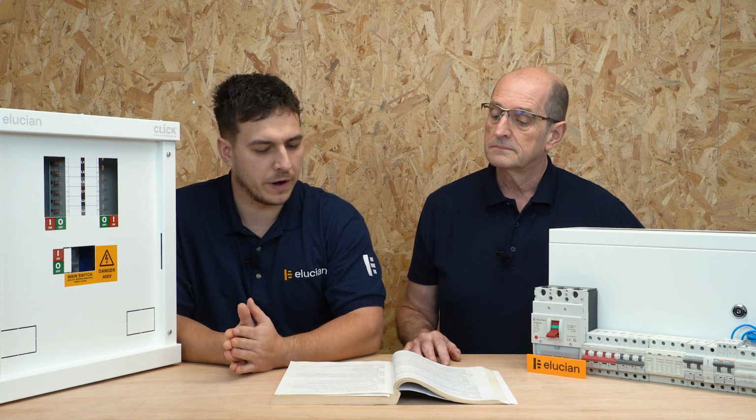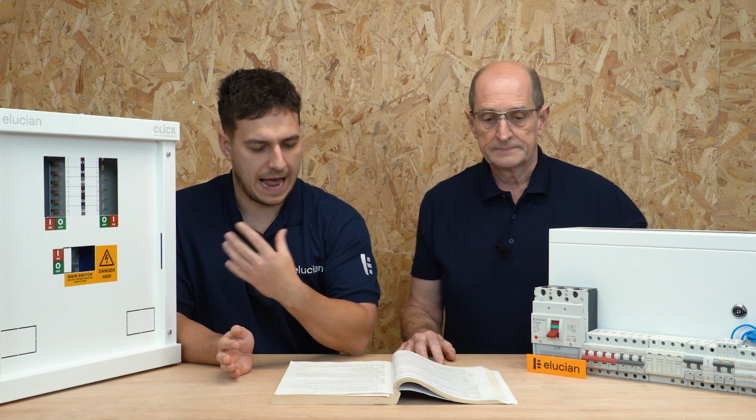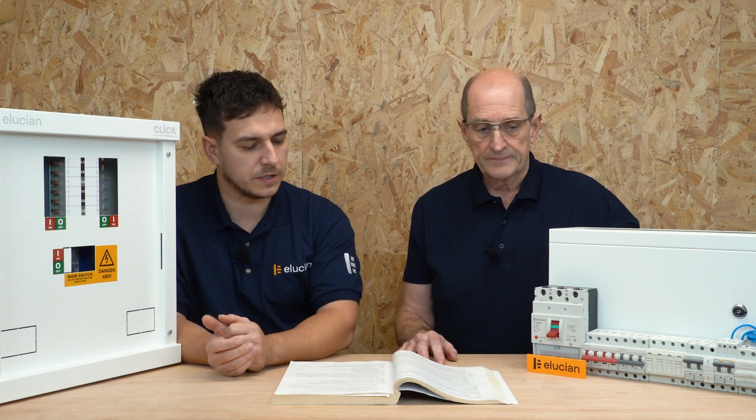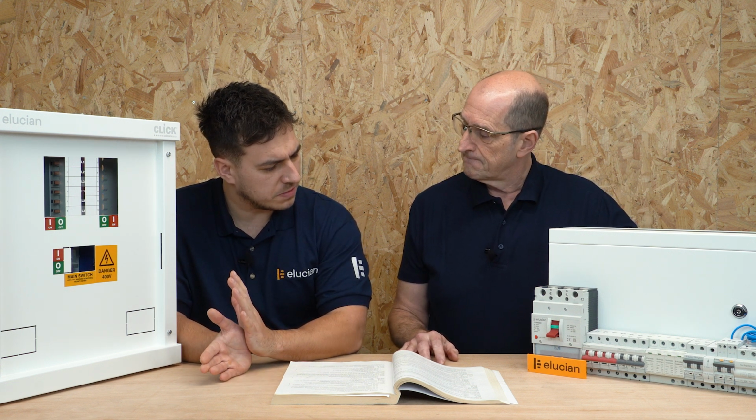Now, that's very important when it comes to the type of installations you're going to be doing when it comes to three-phase and some of the emerging technologies that we've already spoken about. So, subtle differences between the 4 different types, isn't there? Yeah, I mean, the fundamental principle of operation of all of them is the same. It looks for an imbalance between the line and neutral current in a single-phase device or between the line conductors and neutral in a three-phase device. And so the fundamentals haven't changed.